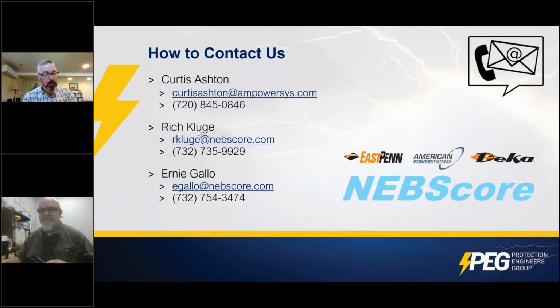I got yelled at one time for pointing out that in a telecom office, you can have different battery power plants on different floors. To the traditional guys that are building commercial grid systems, that was unheard of. Everything is a dedicated building with this. It's all in one spot. They were shocked to hear that you can have a power plant in the basement, and the 3rd floor, and then the 6th floor, and that you had to look at each floor separately and not the building as a whole. So that's a good point. That's another nuance to telecom that's not universal.